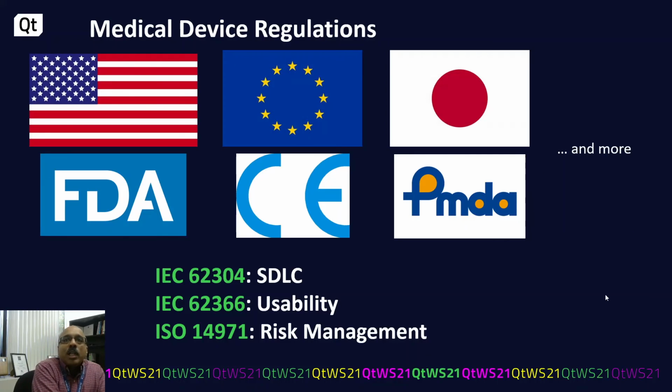Coming to the regulatory side, by working in the medical device industry, we have to comply with several standards. In the US, of course, it's FDA. The EU has CE. Japan has PMDA, and many countries have their own standards, and these standards in turn rely on international standards such as IEC 62304 for software development lifecycle, usability 62366, and risk management, which is ISO 14971.